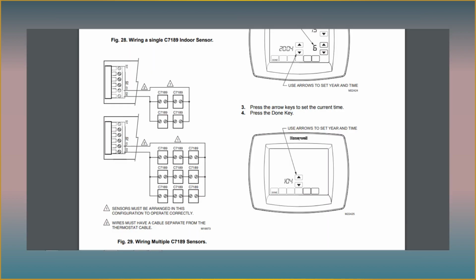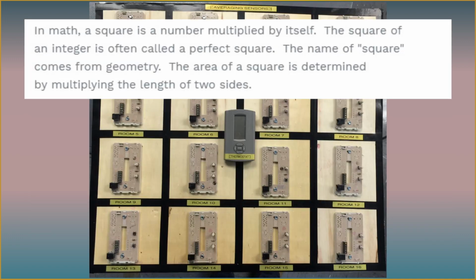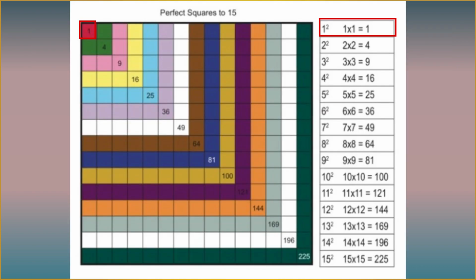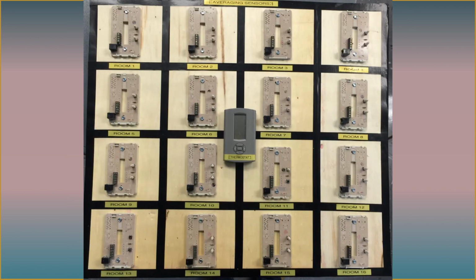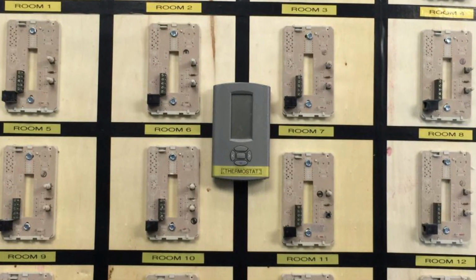In addition, with the remote sensor function, you can also hook up multiple sensors in different rooms, all wired together to report one average temperature reading of all 4 sensors. Now, you can hook up as many sensors as you want, as long as the total number of sensors equals a perfect square. Now, a perfect square is a number or integer that when multiplied by itself equals a perfect square. For instance, 1, 4, 9, 16, 25, or even 36 sensors. But using 1 or 4 sensors is the most common method.